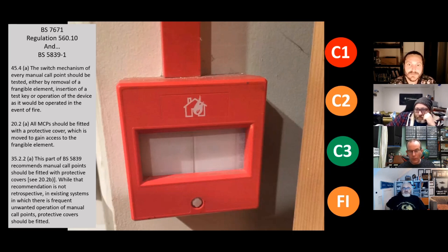Even if you're going to the wholesalers to get a replacement, there's a valid comment from Dean. If you work with fire alarms, you'll have done this while going to wholesalers to get a new one. I would argue, if I was a judge, well, if you work with fire alarms, why don't you keep a stock on the van? And if you did go to the wholesalers to get a new one, fair enough, because it may be a special or something you need, have you told the responsible person for the building what the risks are? Have you done that before you've left the building? It doesn't matter if the wholesaler's 5 minutes away or 2 hours away. But it's a valid point, Dean, to be honest with you. I probably wouldn't do that, and I wouldn't condone that. I would make sure there were plenty of spares.